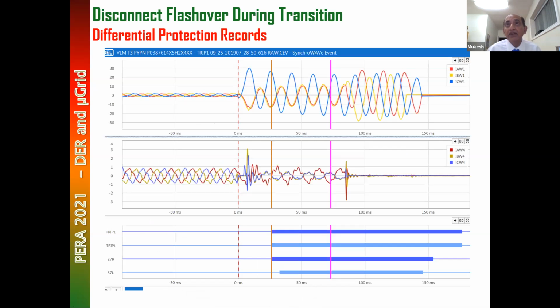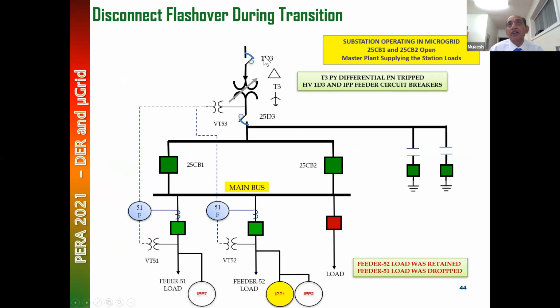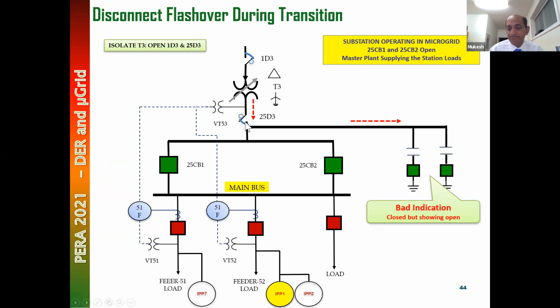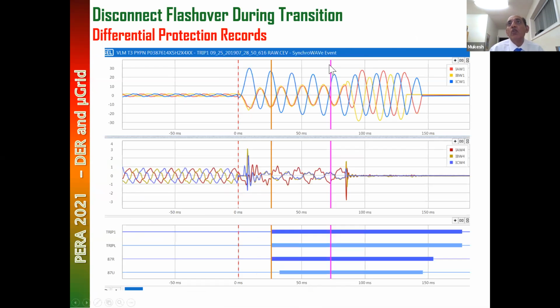And look at what happened. Basically, these are the fault records, one from the low voltage side and one from the high voltage side. Actually, it was a phase-to-phase fault which evolved into a three-phase fault. And look at how much uneven distortion there is on this high voltage side. We did not know about this distortion. Only this fault record told us about it.